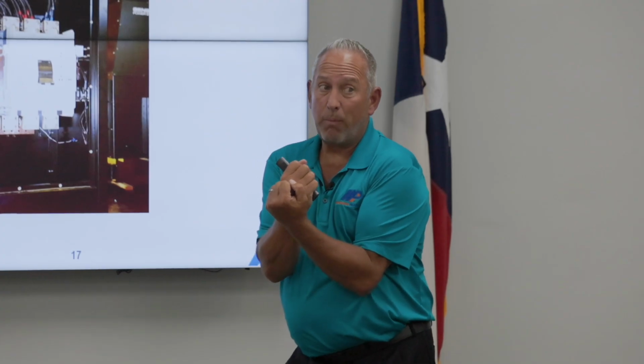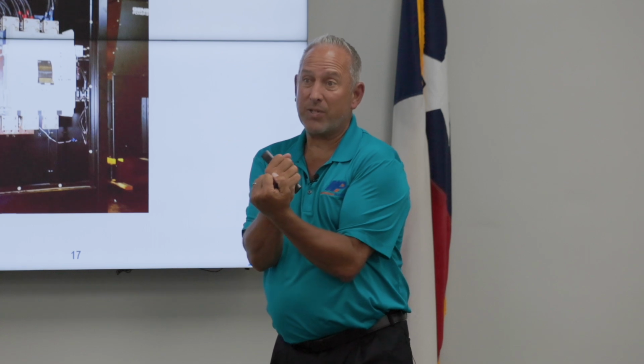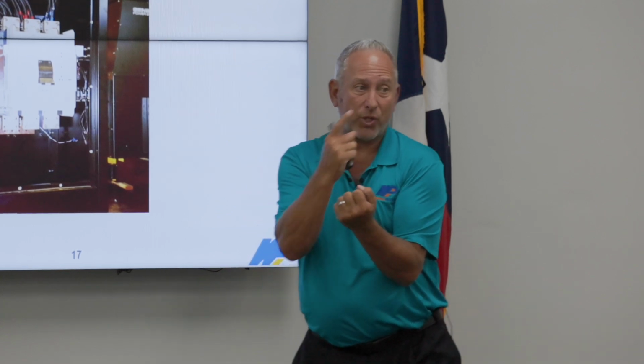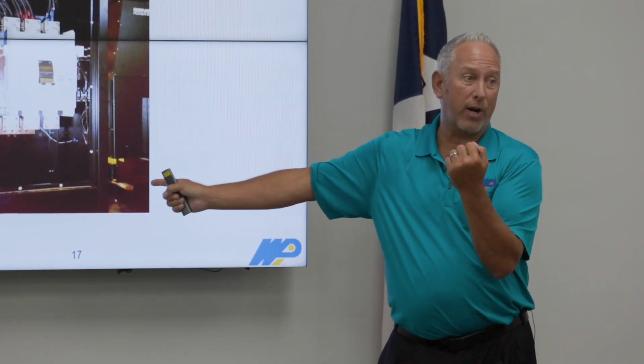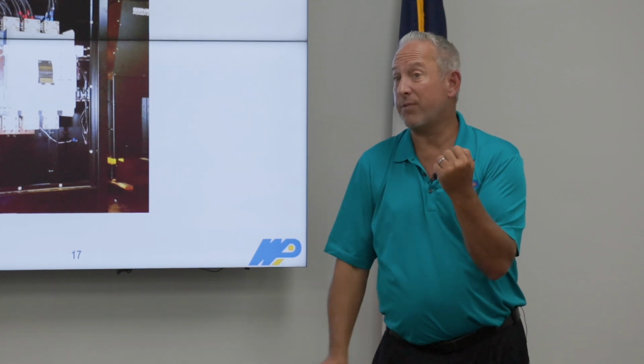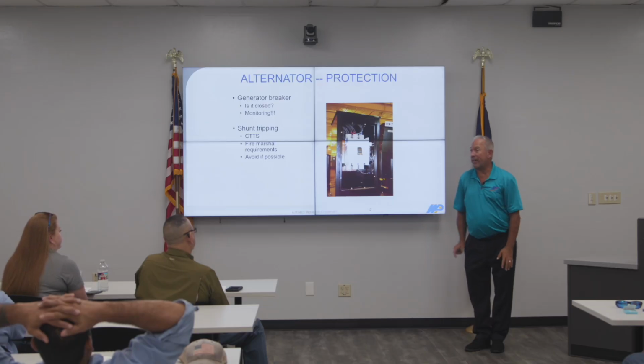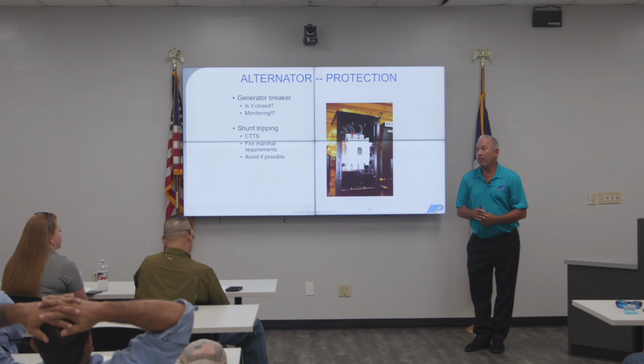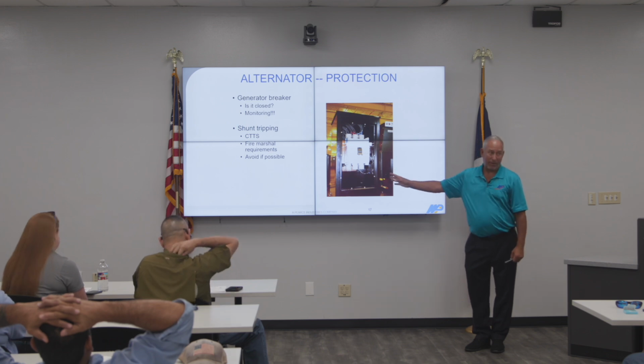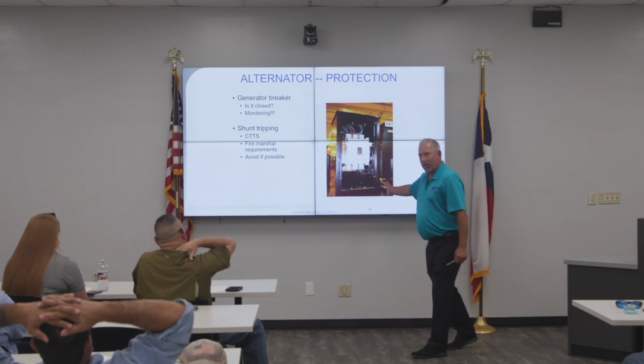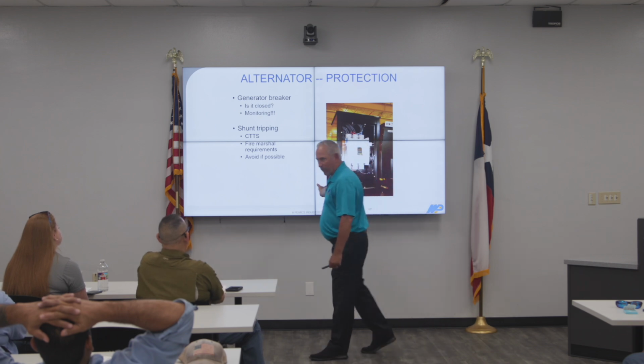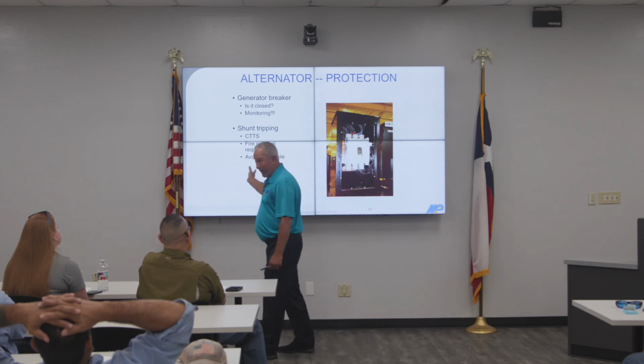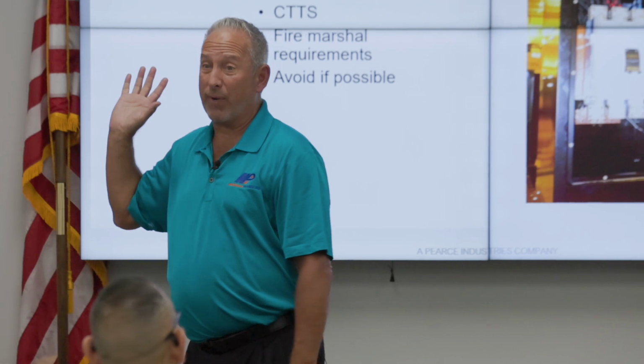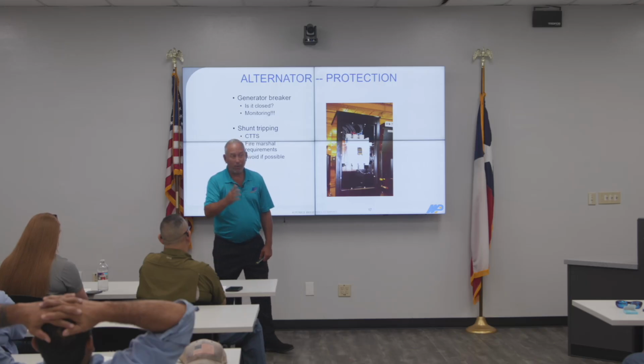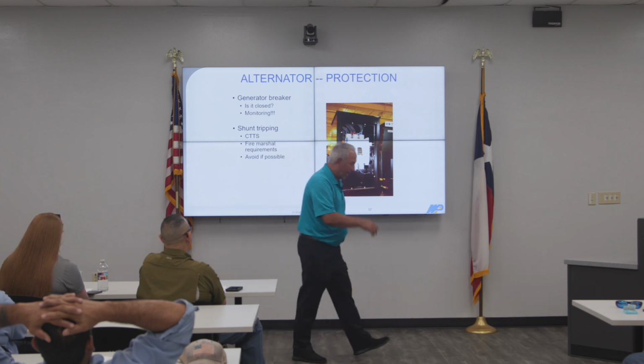If you don't break away in 100 milliseconds, that transfer switch will shunt trip the generator breaker and force it off. So that's the other application. But it's definitely utility driven. So where's the application for this? Hospitals, major data centers, most every single airport, right? NASDAQ stock market was a good example. I used to support them back in the day.